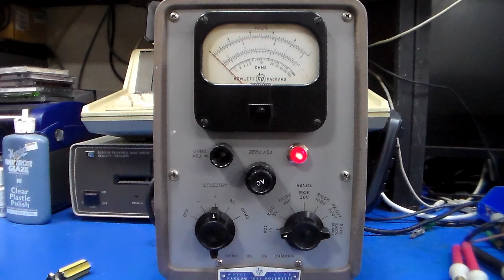When checking the calibration of this meter for the DC ranges, I found that it would set up okay at full scale and read pretty well spot on back to certainly about 60% of full scale, but down below in the region, say 20 to 40%, but really extending from probably about 10% to 50%, the error was starting to increase, and that's to be expected, but it was actually outside the specification given in the HP manual. So I thought, okay, what have we got going on here?